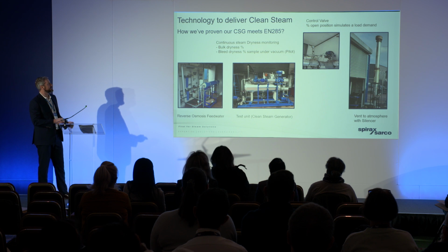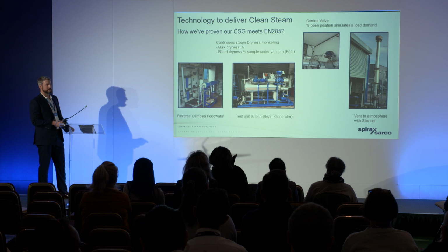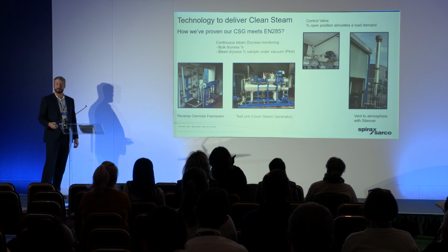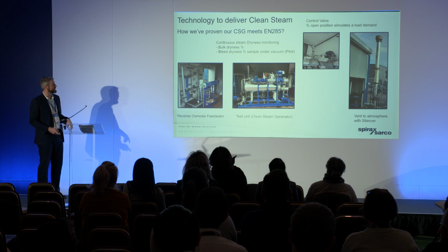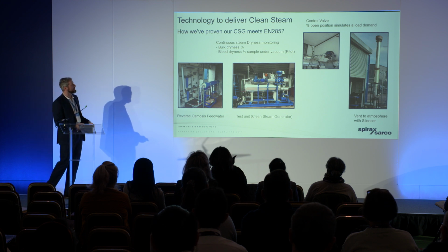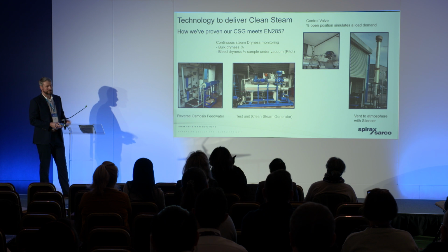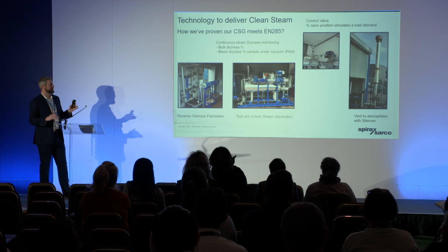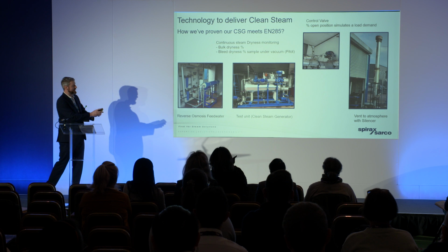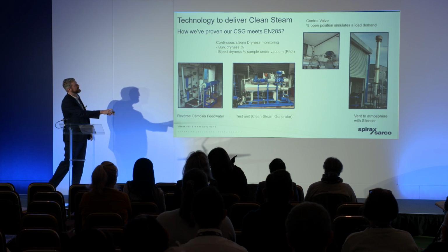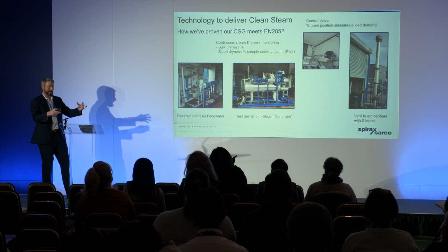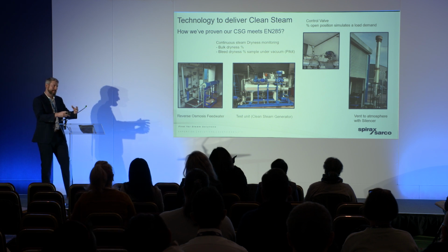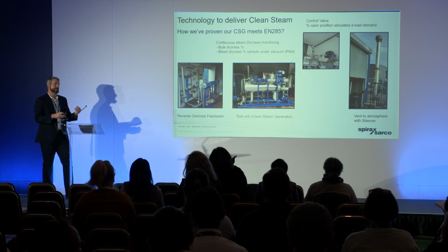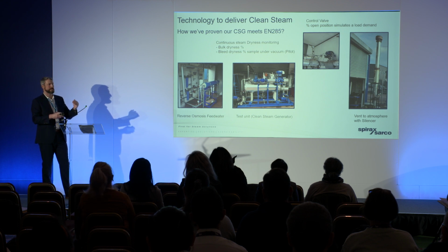We were able to measure the bulk dryness using temperature and pressure, back calculating from the enthalpy, which Sean showed you on the charts, to work out what that dryness would be. The limitation is that, with the pressures we were working at, going down to atmosphere because it vents to atmosphere, using the bulk dryness after the control valve where it all mixed together, we weren't able to measure below 96% dryness at certain pressures.